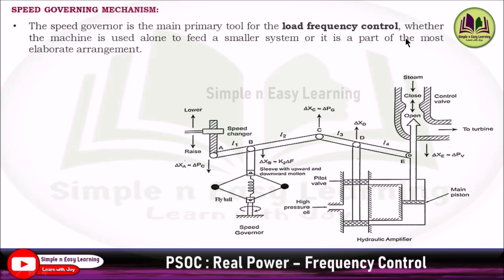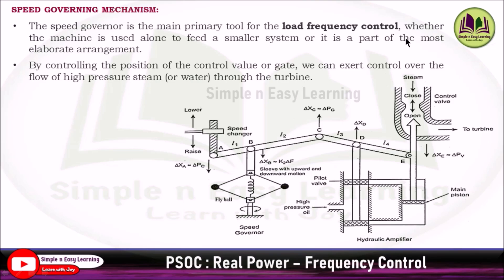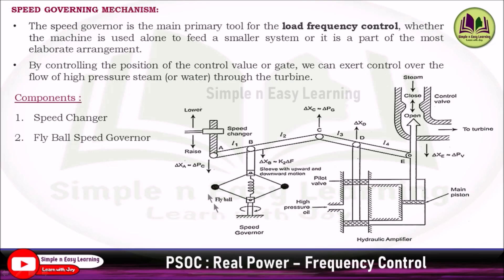The speed governor arrangement plays a very important role in load frequency control. By controlling the position of the control valve where steam enters the turbine, we can control the flow of high pressure steam through the turbine, thereby controlling the turbine speed so that frequency is also controlled. The main components in the speed governing mechanism are: the speed changer, the fly ball speed governor, the hydraulic amplifier, and the linkage mechanism — points A, B, C, D, and E.